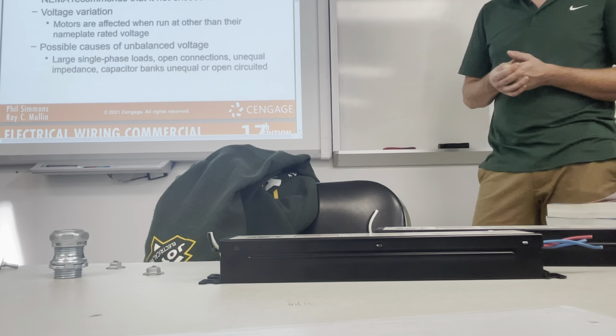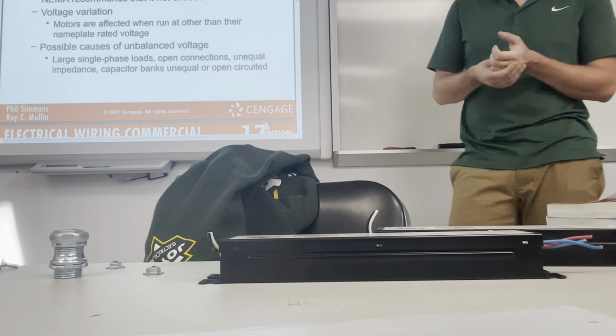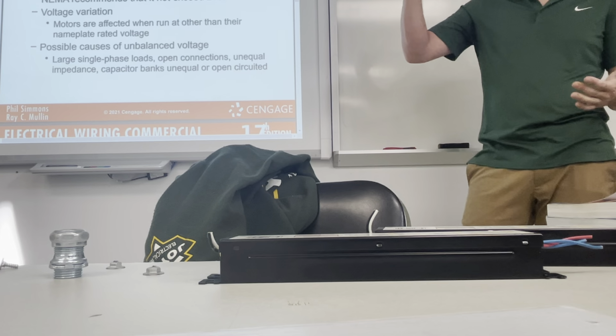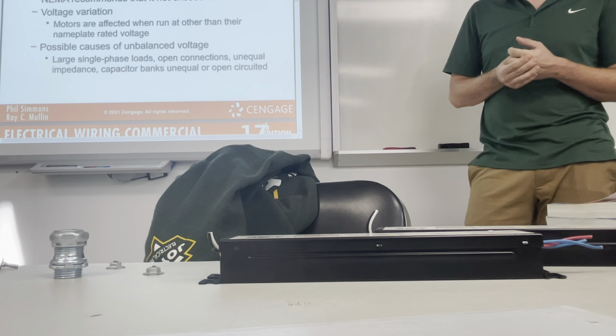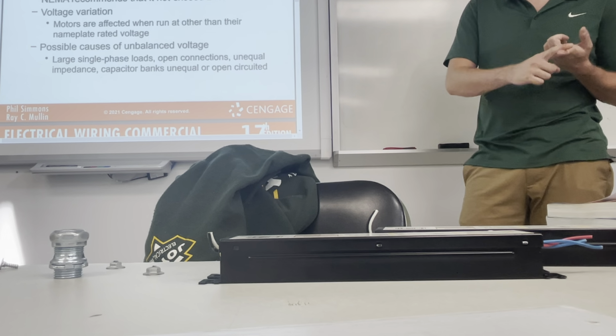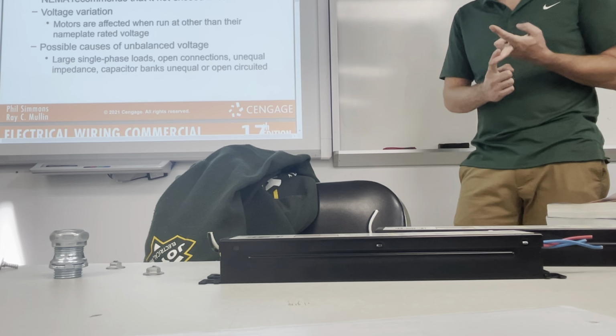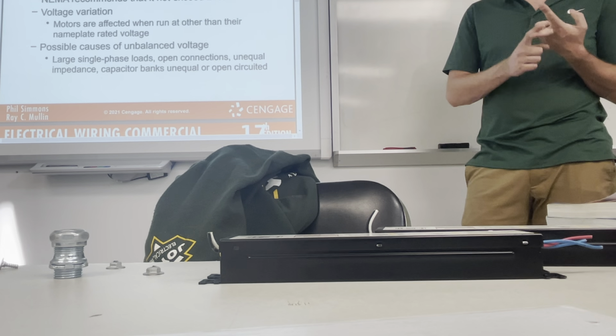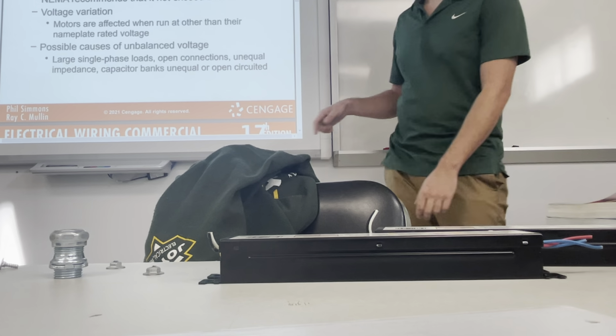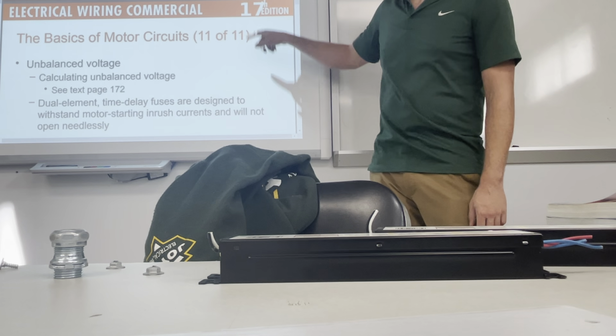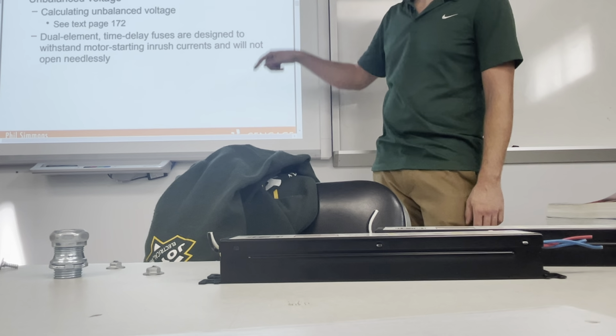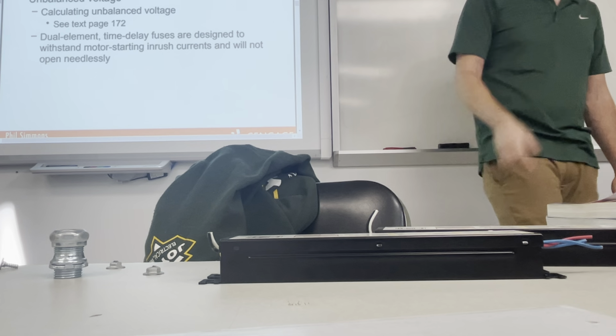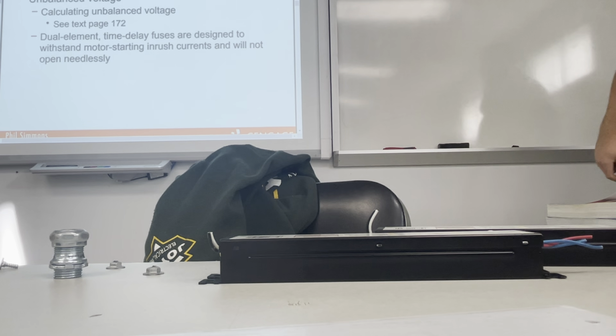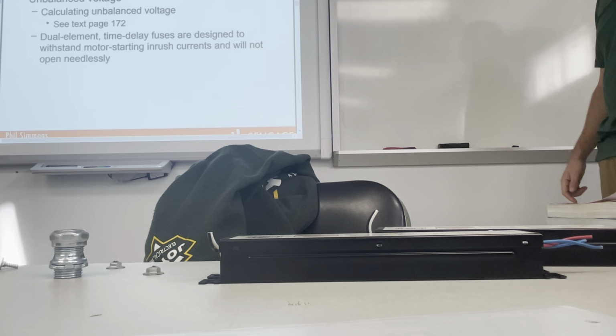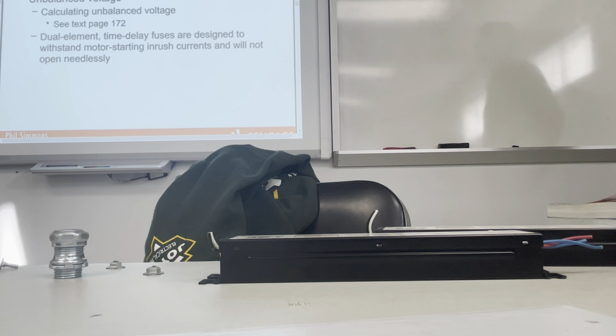Another thing you want to be sure of is to keep all your conductors at the exact same length. If one is a foot longer, it will cause trouble. So with feeders feeding a panel box, they must be the same length. And for motor controls, it's not going to hurt if they're the same length. Unbalanced voltage. Calculating unbalanced voltage.